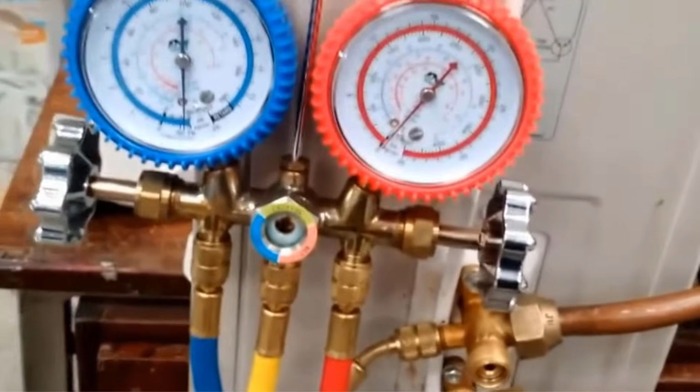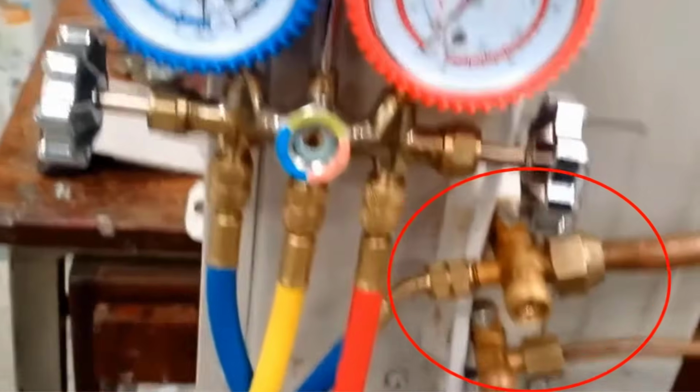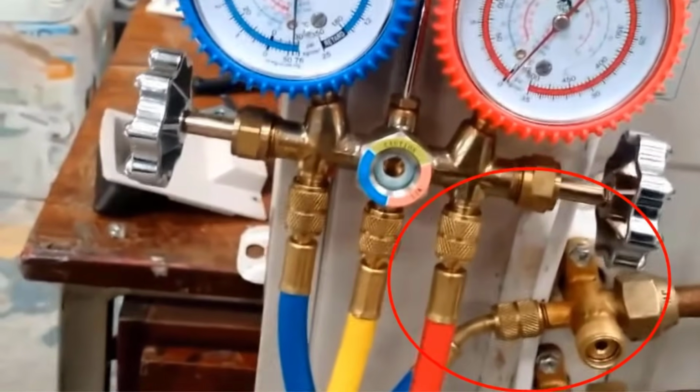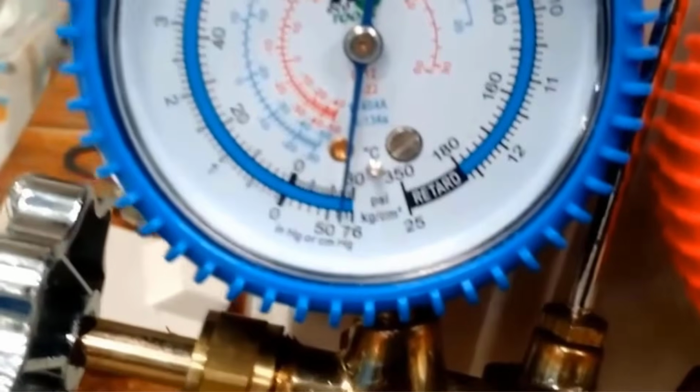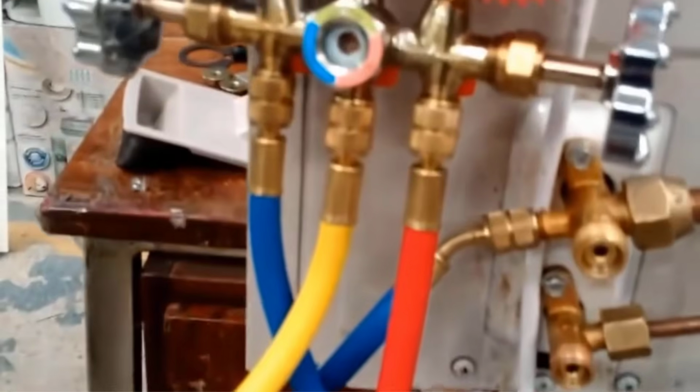Let's start by talking about the service valves. They are located in the condenser and are used by technicians to measure the pressure and replenish the gas. If the air conditioner was recently installed and the valves are not open, the error will appear immediately upon installation. However, if the unit was already working, the problem is probably not with the valves, as they should already be open. In this case, we can rule out this hypothesis and move on to the next possible cause.